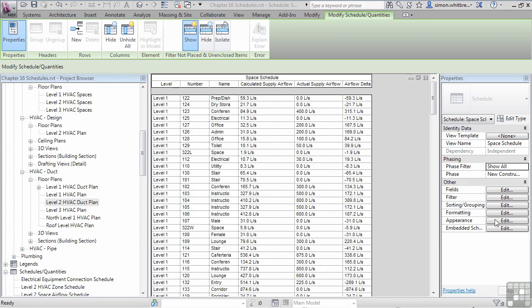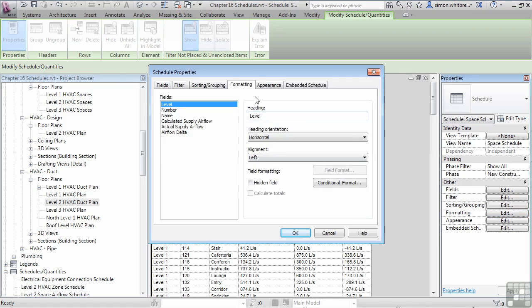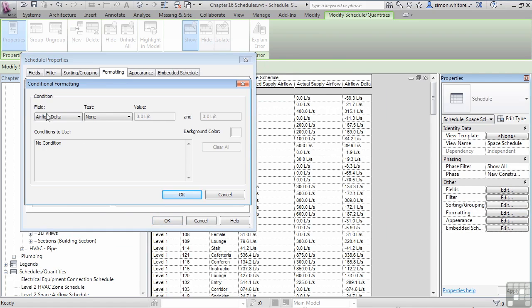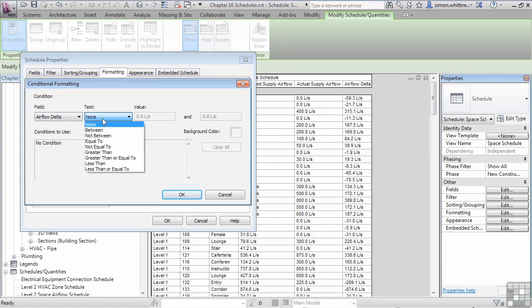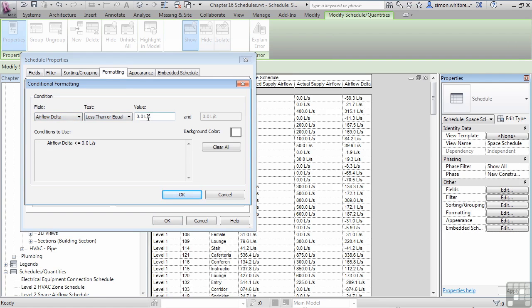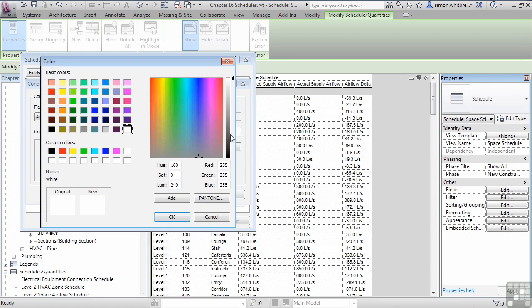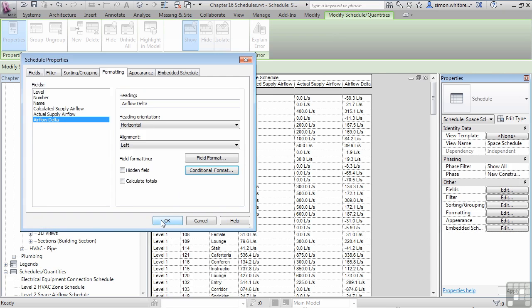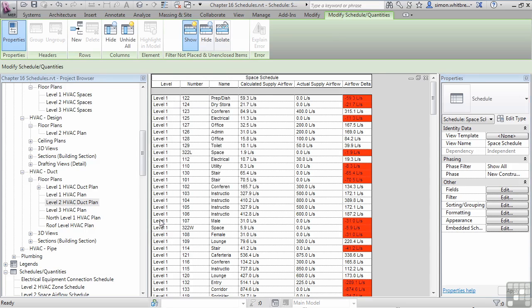From the Properties palette, click on Formatting. Click on Air Flow Delta. And we are now going to add a conditional statement where we are going to say Air Flow Delta is less than or equal to 0 litres a second. We can change the background color to red. Click on OK, OK, and finally OK.